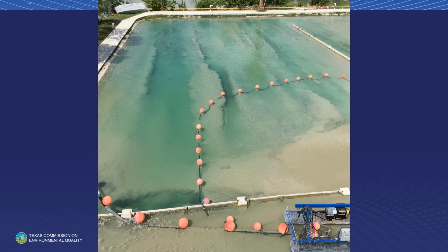This is the plant that had the tanks that they were putting their solids into. This said basin was just a scooped out hole in the ground that they had poured a concrete wall around, and there was no sludge removal in this basin whatsoever. So what they had done is taken pumps and put them on a raft, and they run that raft up and down this basin, and it was sucking sludge up off the bottom of the basin to remove it out of the said basin. It was kind of a unique way to try to do it.